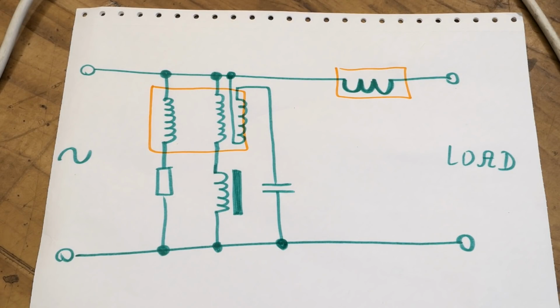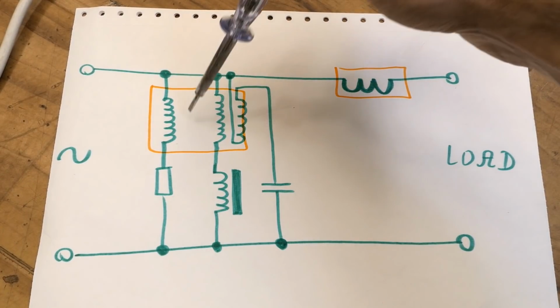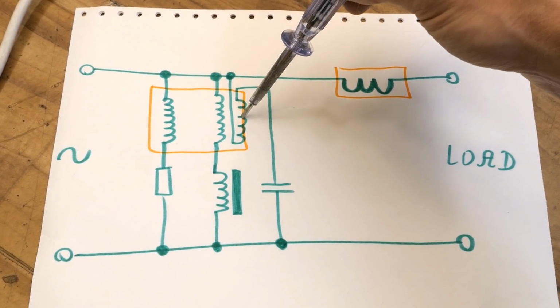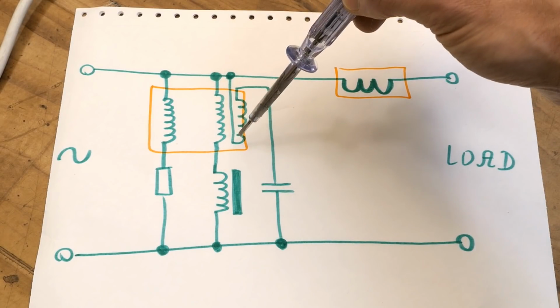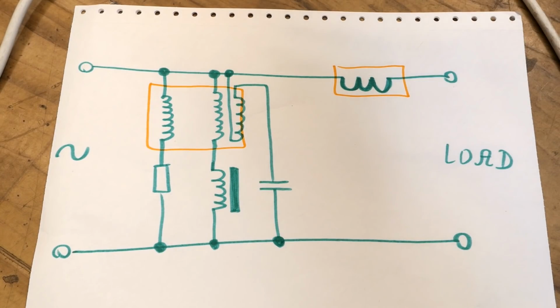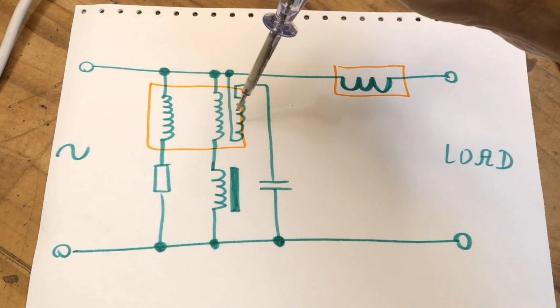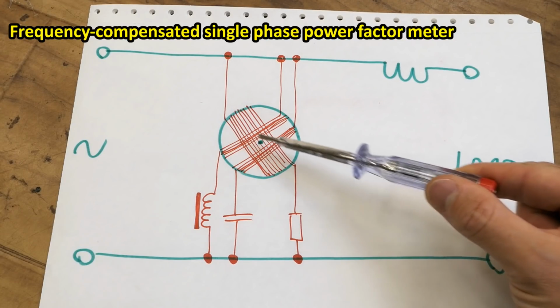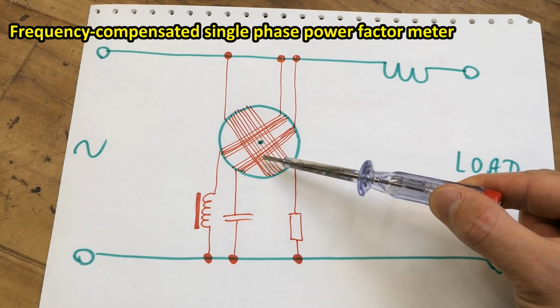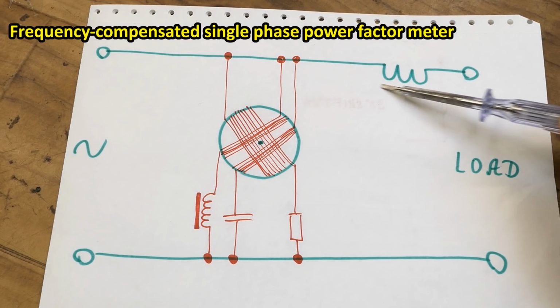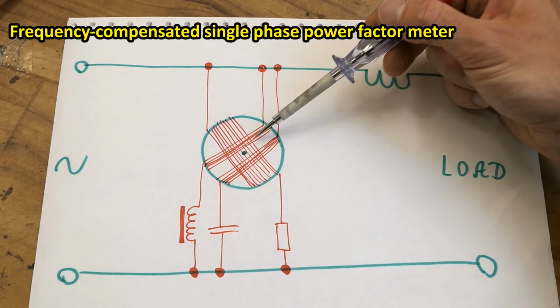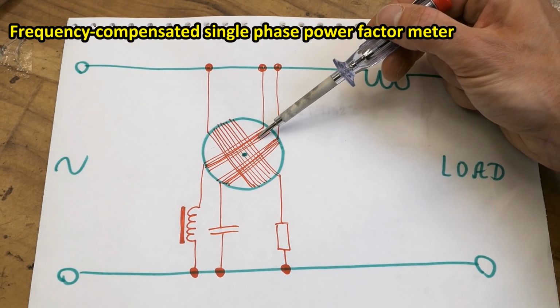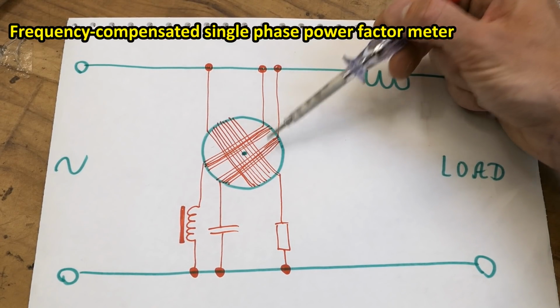The frequency dependence can be cancelled out by having 3 voltage coils, one connected via a resistor and 2 coils connected, one via an inductor and one via a capacitor. And of course this one is 90 degrees in reference to these ones. 3 moving coils, voltage coils in the magnetic field of one current sensing coil. And of course these two are polarized in such a way that the magnetic field is adding, not cancelling out.